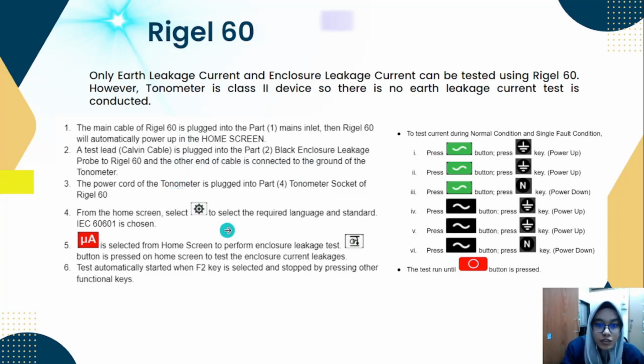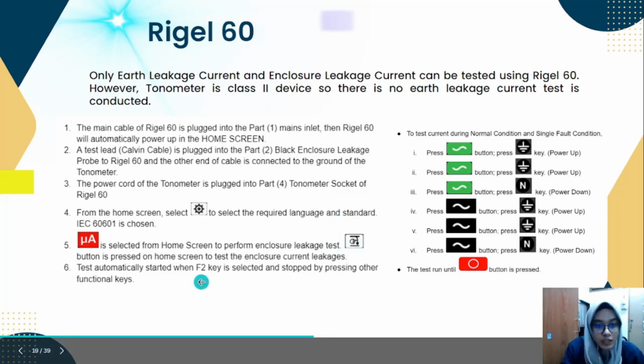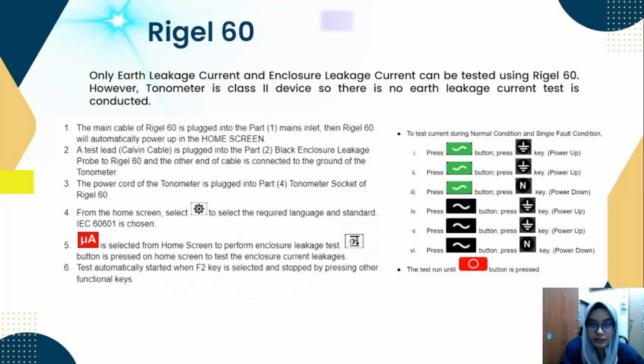To perform the enclosure leakage test, this button will be pressed and the test will automatically start when the F2 key is selected. To test the current during normal condition and single fault condition, we can follow this sequence to have the test conducted fully. Then, after the test finishes, this button will be pressed and the test will stop.